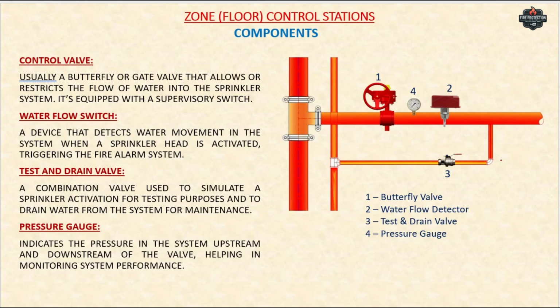Now let us understand the basic components of the floor control station. See, the first is the control valve. This control valve can be either a butterfly valve or a gate valve. The control valve basically restricts the flow of water into the sprinkler system. It's strictly a supervisory valve. Here we have one supervisory valve which is connected to the fire alarm panel.